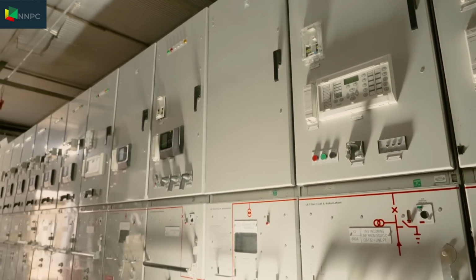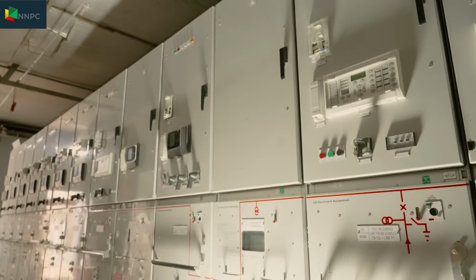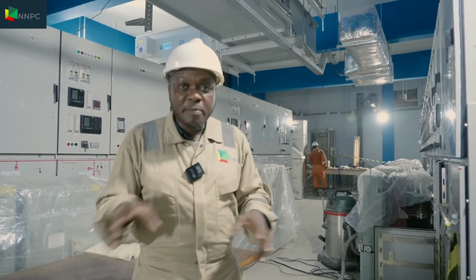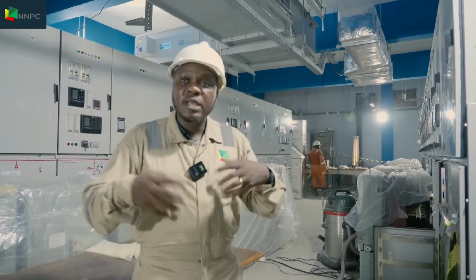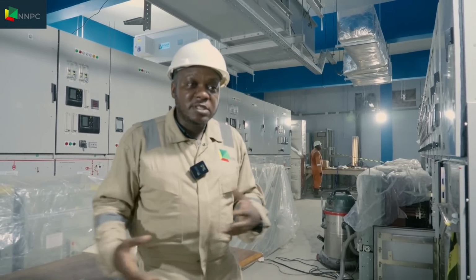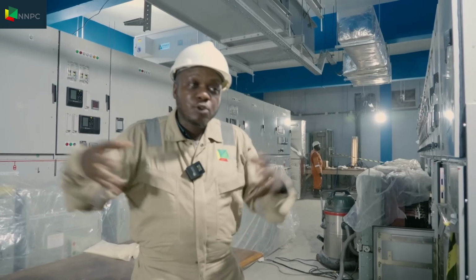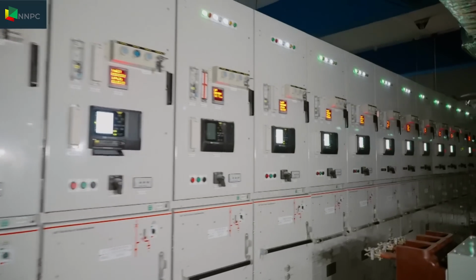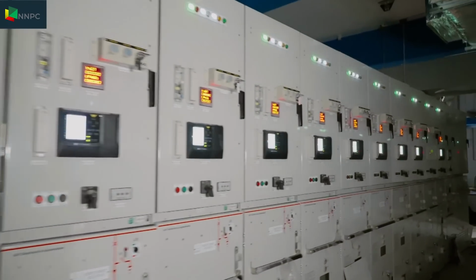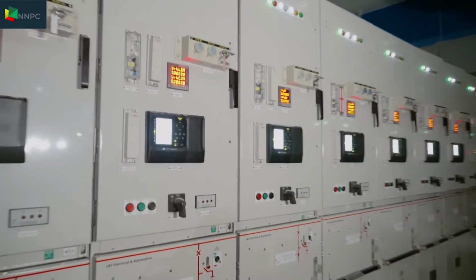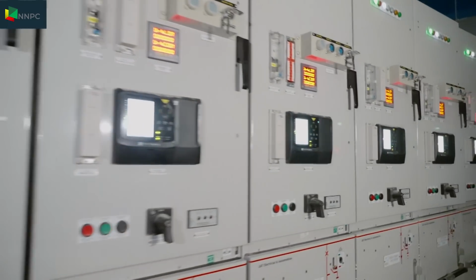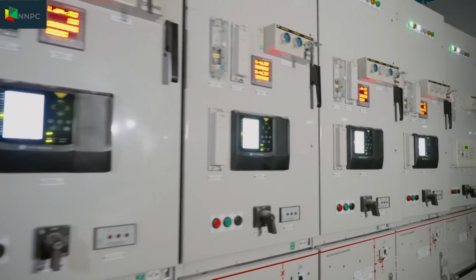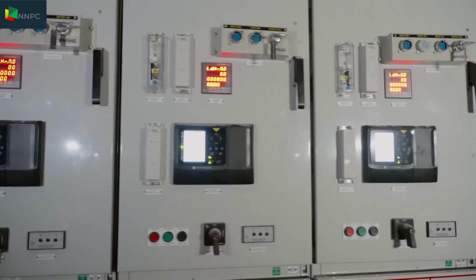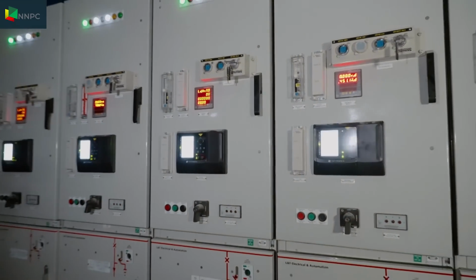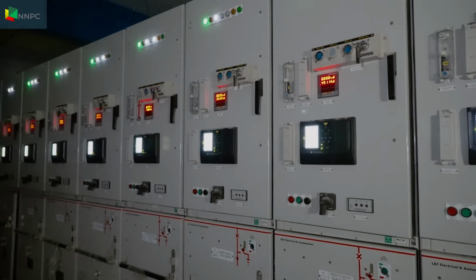It never comes down. It was a big contention even during the design phase that took us close to 3 months to figure out. We, with the PHRC team, the PMC team, and the contractor, had to come together and put our heads together. The substation, which contains high voltage panels, low voltage panels, and motor control center panels, receives 11,000 volts of electricity. From here, it is stepped down for distribution to other substations.